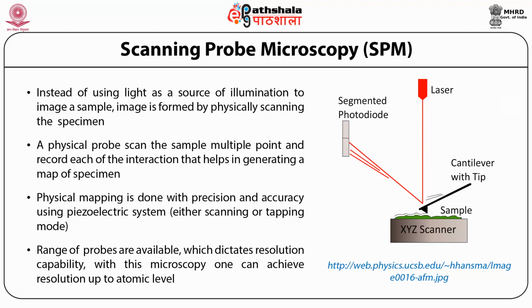For example, in this picture, as you can see, a laser is pointed toward the cantilever tip and the cantilever tip is scanning the entire sample. Depending upon the depth and the height at which the contact is made, that information is directed toward the photodiode, which is used to construct an image based upon the interaction pattern that the cantilever experiences. This mapping is very fine and can be very high resolution because the cantilever tip is moved using a piezoelectric system, whether by scanning or by tapping mode. In both processes, the mapping is highly motorized and highly controlled.